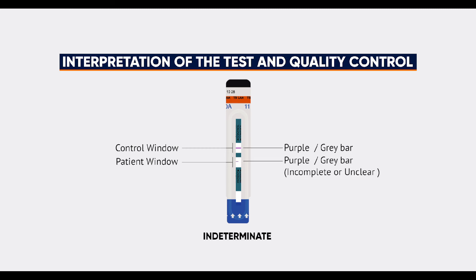If one purple or grey bar appears in the strip's control window, labelled control, with an unclear or incomplete purple or grey bar in the strip's patient window, labelled patient, the TB-LAM result is indeterminate. For a better clinical decision, the test should be repeated. Alternatively, collect a new urine sample in the following days from the patient and test — early morning urine is recommended.